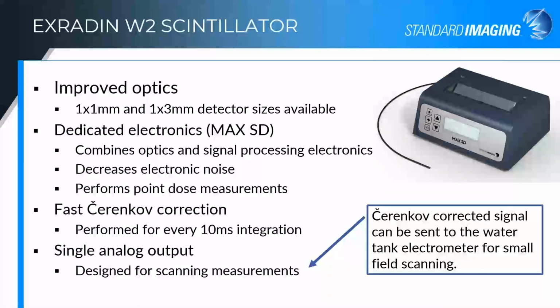With the W2, this was our second generation device. We were able to improve the optics in order to allow a decrease in the active region of the scintillator without compromising on signal to noise. So we were able to go down to a 1x1 millimeter scintillator. We also provide it with a 1x3 as well, because there are so many W1 publications, including TRS 483, that refer to the output and the response of the W1. That provided a nice link for some people back to those W1 publications. It also gives you 3 times the signal. So your signal to noise as you're in the mid-range of those small fields rather than the teeny tiniest ones is nice from the larger field.